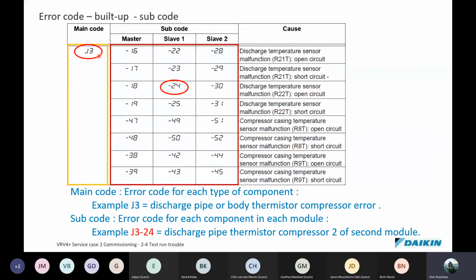So here we see a J3-24 is a discharge temperature sensor malfunction of an R22T, and it says it's open circuit. If it's open circuit, what it's telling us is the thermistor is giving an open circuit reading back to the PC board. This could be the thermistor's faulty, or possibly the PC board might be faulty. And the -24, or the 24, tells us to look at the slave 1. So here it's making life easy for you. You see the J3, you don't need to look at the master or slave 2, you need to go to the slave 1 condenser.